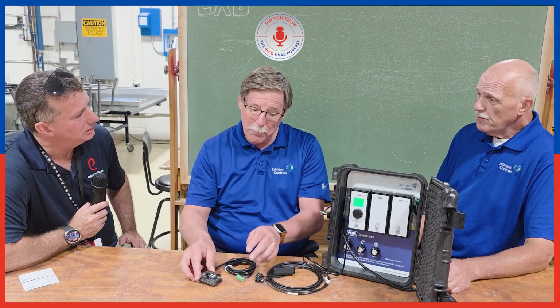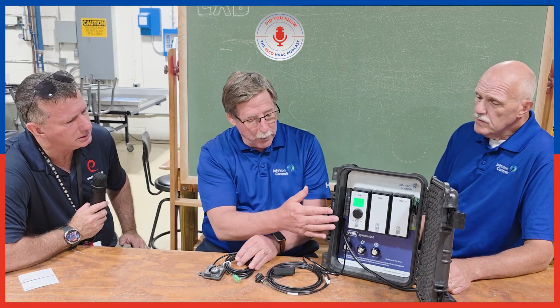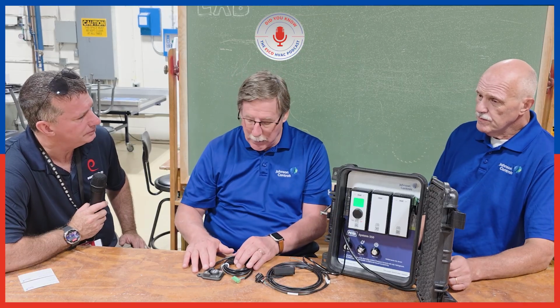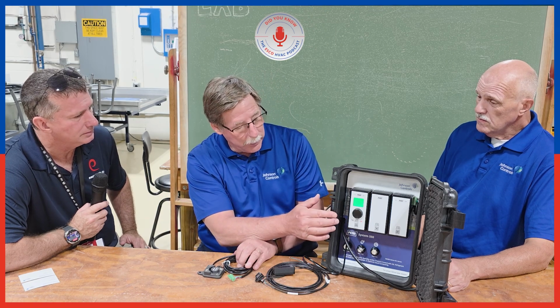No joke. So if I have a large piece of equipment, maybe a packaged rooftop system, and I have to use multiple sensors, in addition to selecting the refrigerant type, I'll select the number of sensors that I use. And our particular controller's factory setting for the digital trip point on the A2L is 20% LFL, or lower flammability limit. Sure. You bet. If you want to warn below that, you also have the capability with this controller to set an LFL level lower than that digital trip point for a different alarm set point. Yes.